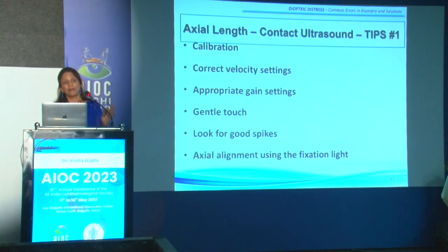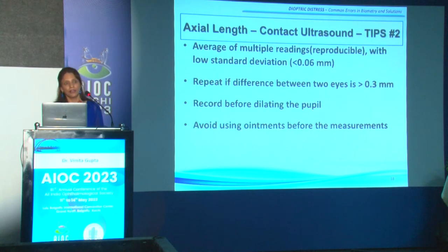Ensure that there's axial alignment, which is very, very important when you're doing measurements with any biometer. And in this, for ultrasonic, by asking the patient to look into the fixation lights. Again, take the average of multiple readings with a standard deviation between each reading less than 0.06 millimeters. Repeat if the difference between the two eyes is more than 0.3. Preferably always take measurements before dilating the pupils.